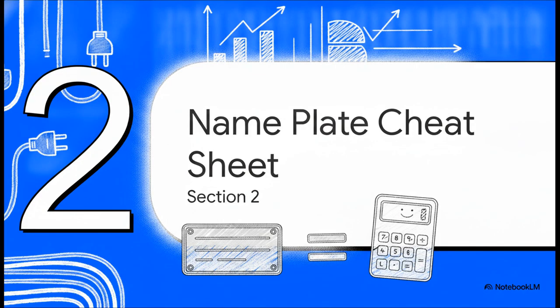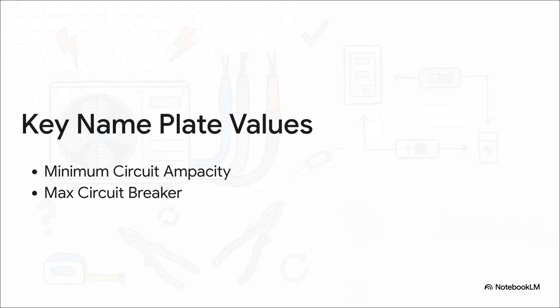Moving right along to part two, the nameplate cheat sheet. Now, since we're operating under a totally special set of rules, you might be thinking the math is going to be an absolute nightmare. But actually, the industry hands us a master key: the equipment nameplate. Every listed AC unit has to have one. You just need to find two vital numbers provided by the manufacturer: the minimum circuit ampacity, or MCA, and the maximum circuit breaker or fuse size, which is sometimes called the MOCP. These two numbers are literally the only starting points you need. They already account for motor characteristics, those crazy high starting currents, and all the internal loads.